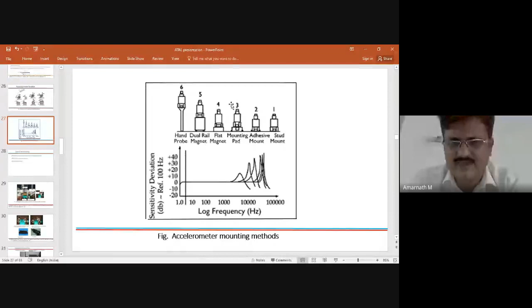But there are some applications where we are not going to use a stud. For example, if you want to measure the vibrations of a turbine blade, it is not possible to drill a hole. So for such applications, we use either magnet base mount or adhesive mounting methods. Normally, for complex machinery, we use the stud mounting method. The magnetic base mount method is also used in acquisition of vibration signals from a tool holder. So based on the system, we select the mounting method.